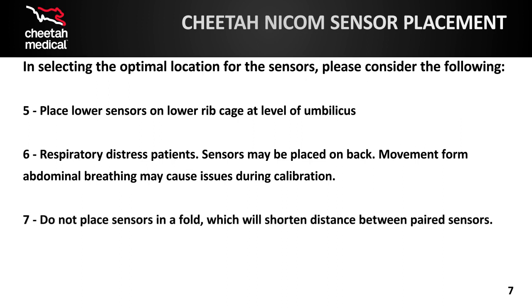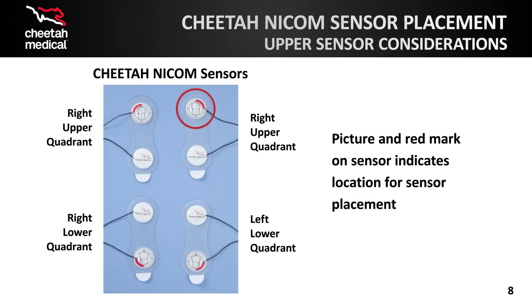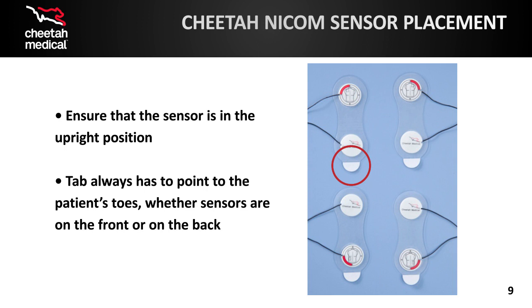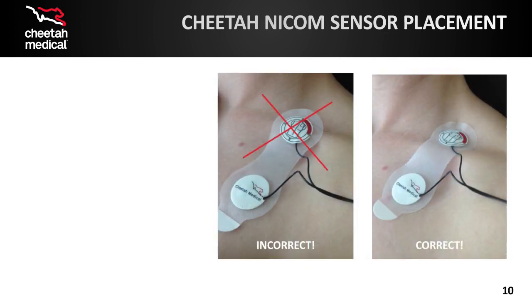7. Do not place sensors in a fold, which will shorten distance between paired sensors. As mentioned previously, there is a red indicator located on each sensor which directs one to the proper sensor location. Always ensure the sensor is in the upright position, with the small white tab pointing toward the patient's toes. Now, let's review the things to consider for application of the upper set of sensors.